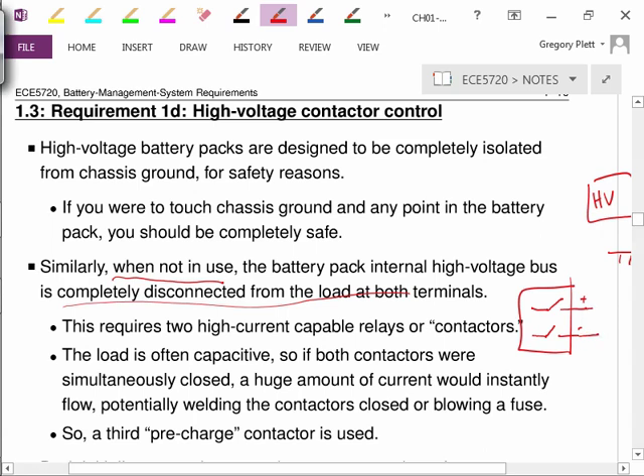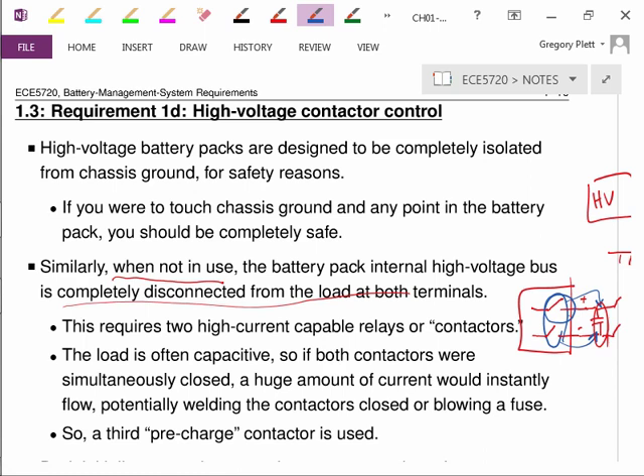But the load usually has some capacitive nature to it, especially if I have a motor control, because the motor control itself has a lot of switches, which adds a lot of noise, and they put capacitor banks on these switches in order to smooth out the load demand. So a capacitive load is not uncommon. And if I were to close both of these contactors at the same time, the current would try to charge up this capacitor instantly, because there's essentially no resistance or extremely little resistance of the wiring between the battery pack and the capacitor. An enormous amount of current would flow out of the battery pack, which is going to exceed the design limits of the wiring, and furthermore, it could cause arcing inside of the contactor, even across a vacuum, and that could cause welding of the terminals so that they could never open again, so you'd always have just a contacted contactor. Or you could even blow a fuse if you have a fuse in your battery pack, and you probably do.